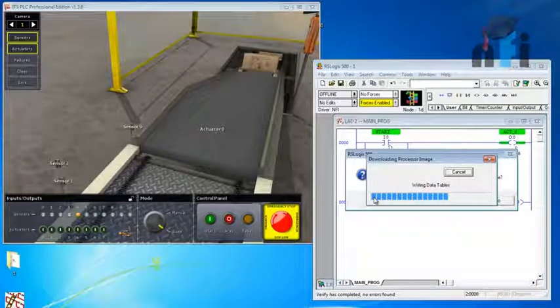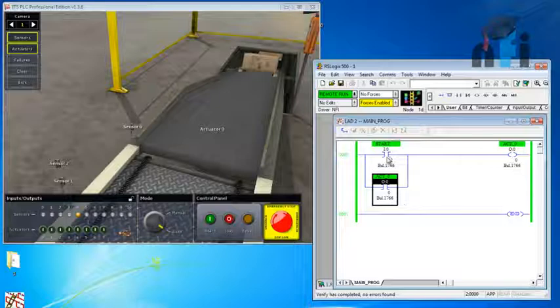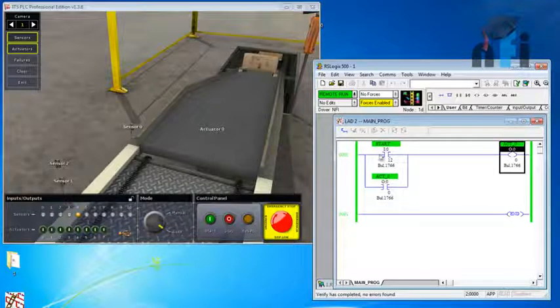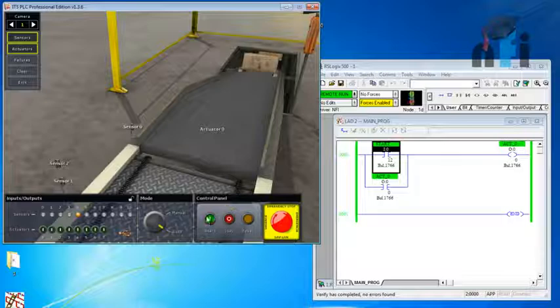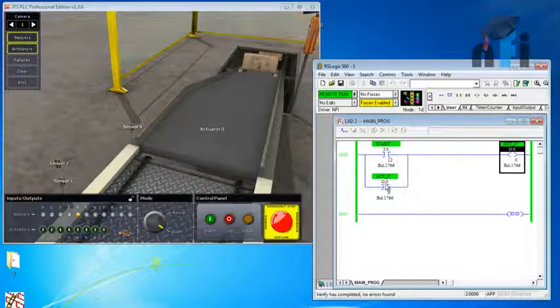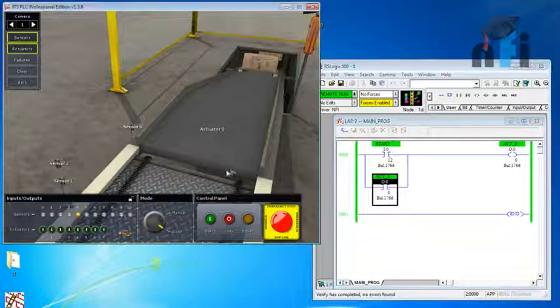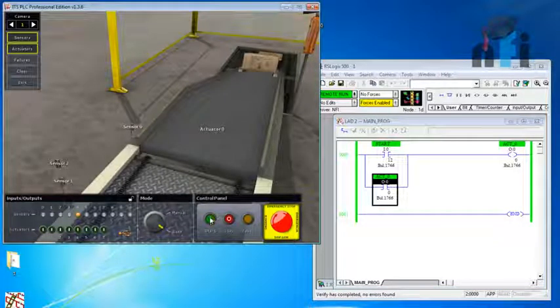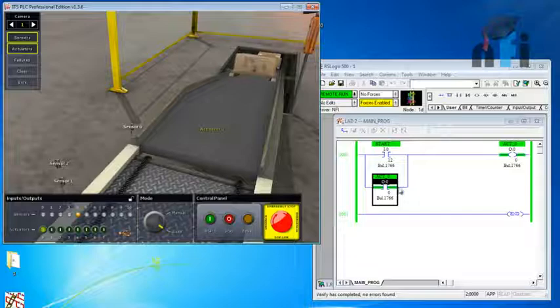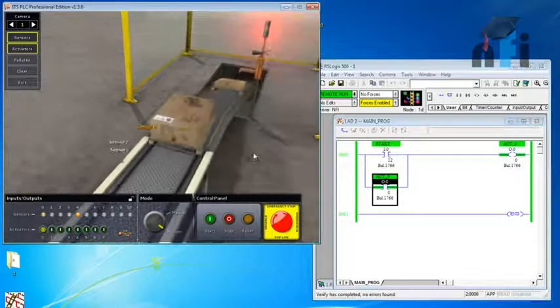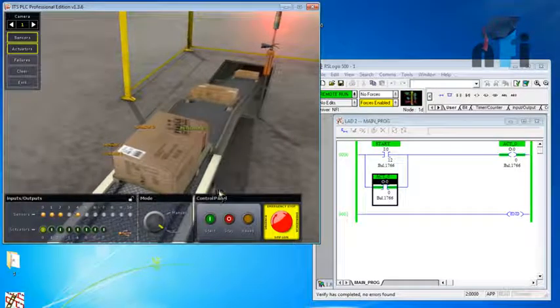Let's download and see the results. Once I press the start button, the output turns on and since the parallel rung has the same address, it also turns on, providing a parallel signal path to keep the output active. I'll press once and release — the output remains on because of this parallel rung. This is called latching.